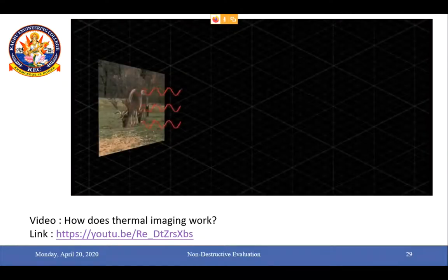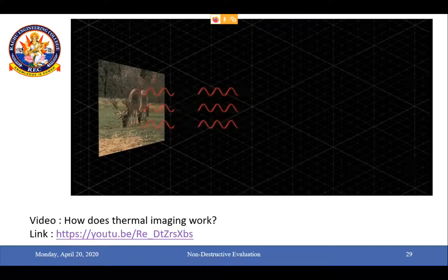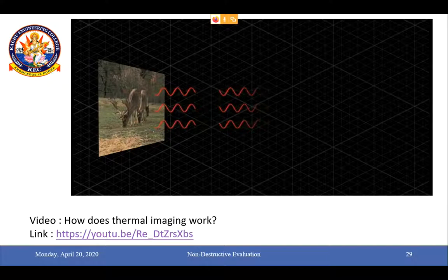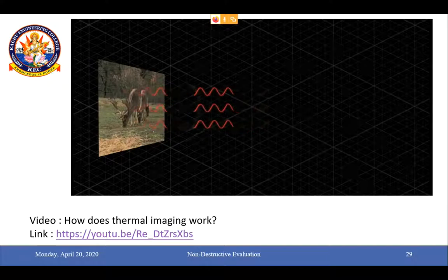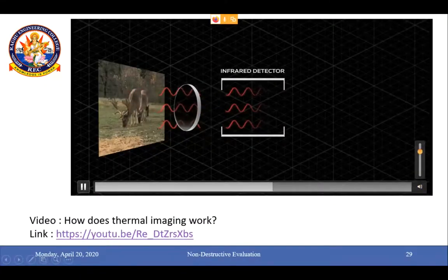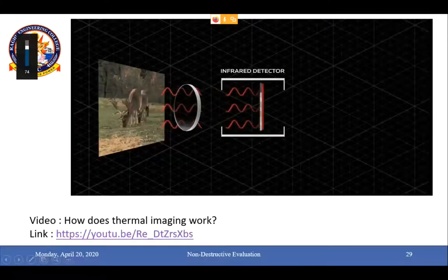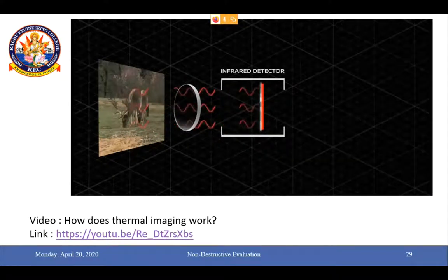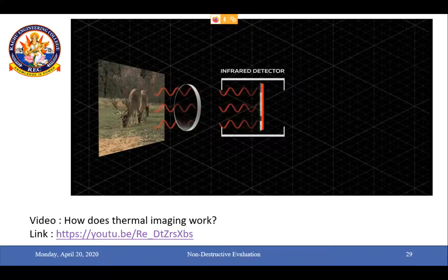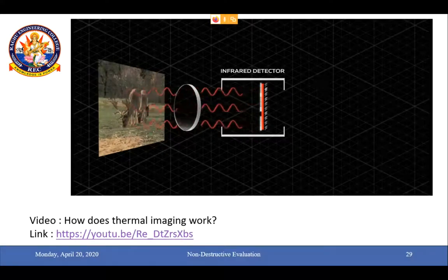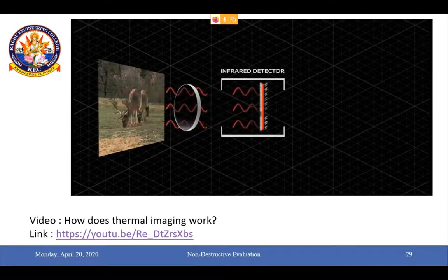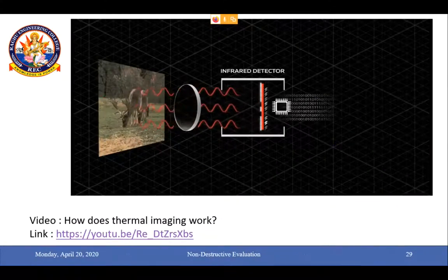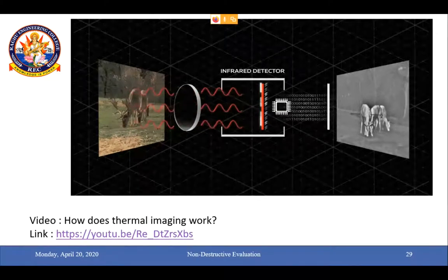Thermal imaging devices work in the infrared spectrum of the light. Each object of the scene emits infrared waves in the form of heat. The infrared waves are captured and transmitted by the IR objective made from the sophisticated crystal germanium and then focused towards the infrared detector of the thermal imaging device. The infrared detector is composed of tiny sensitive elements, commonly known as pixels. These interact with the infrared waves and read them, while at the same time they generate electronic impulses with different values. These impulses are then processed by the electronics to a digital image that is viewed on screen in the viewfinder.